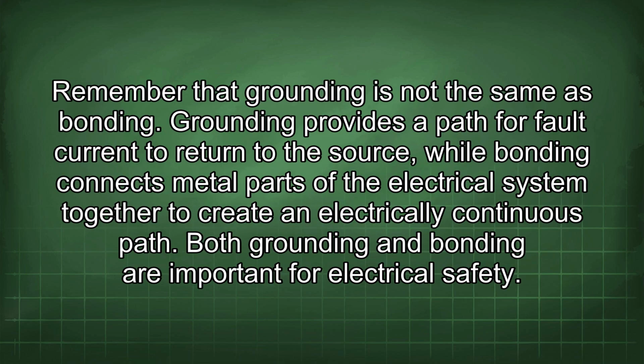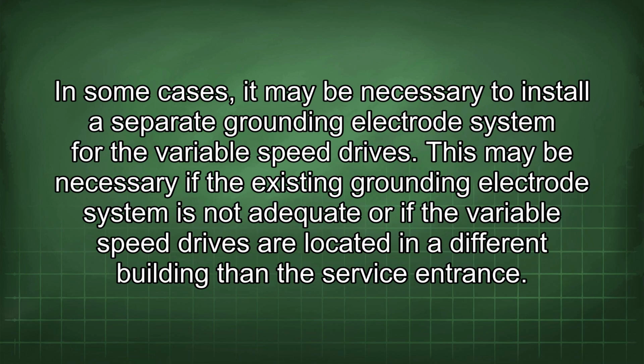Remember that grounding is not the same as bonding. Grounding provides a path for fault current to return to the source, while bonding connects metal parts of the electrical system together to create an electrically continuous path. Both grounding and bonding are important for electrical safety. In some cases, it may be necessary to install a separate grounding electrode system for the variable speed drives. This may be necessary if the existing grounding electrode system is not adequate or if the variable speed drives are located in a different building than the service entrance.